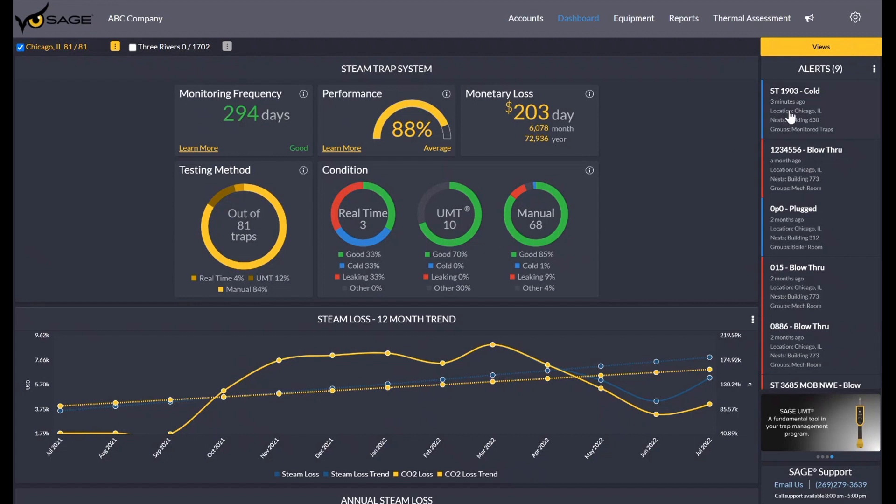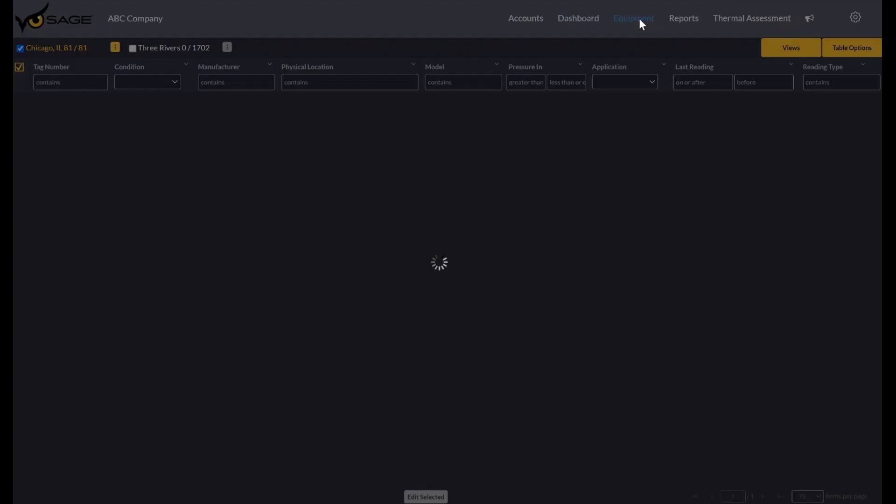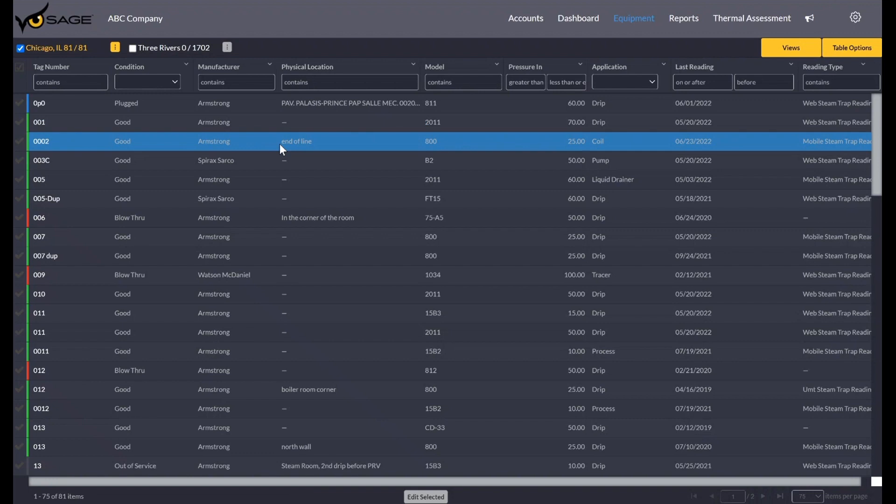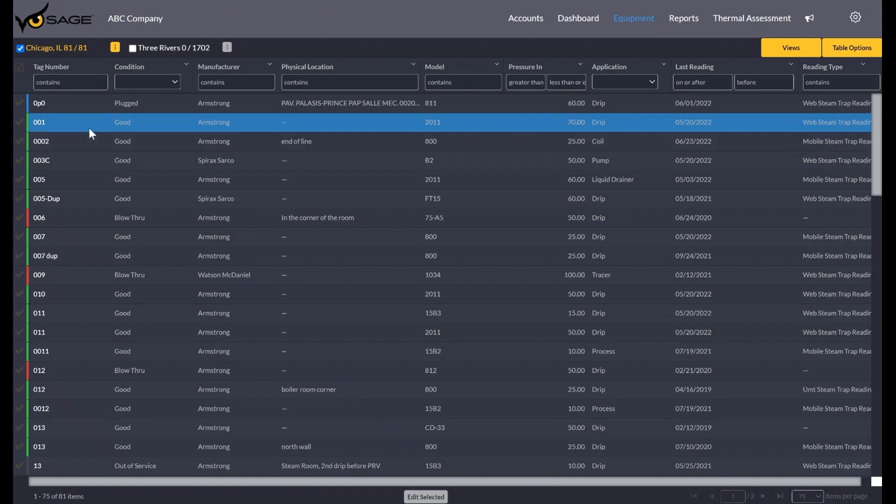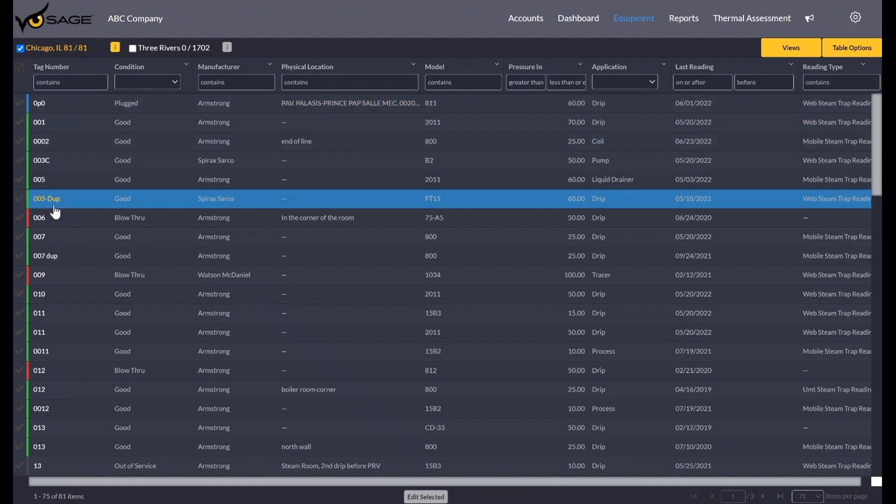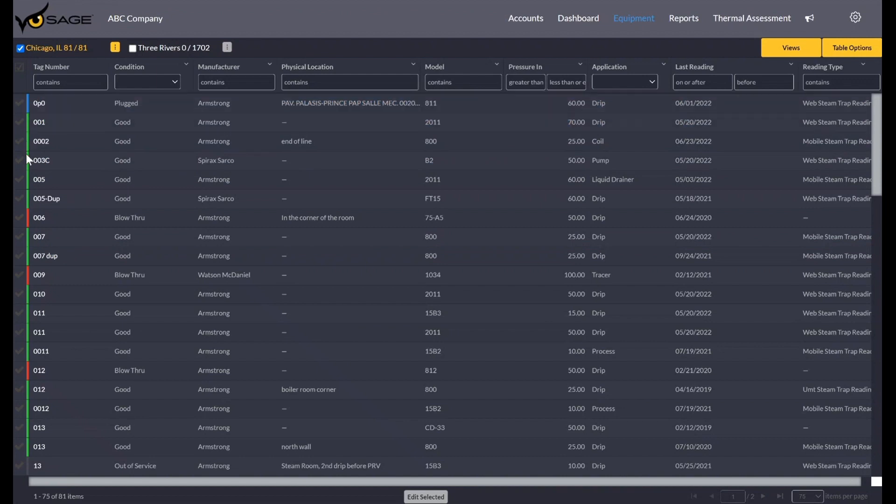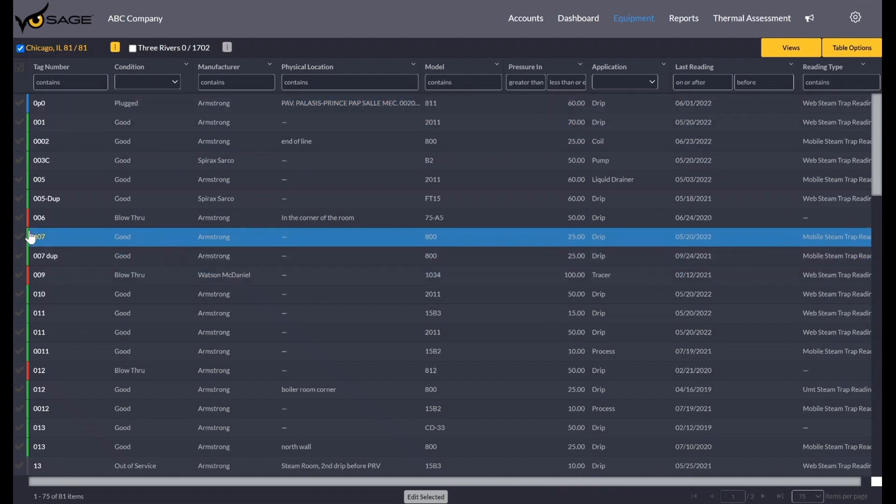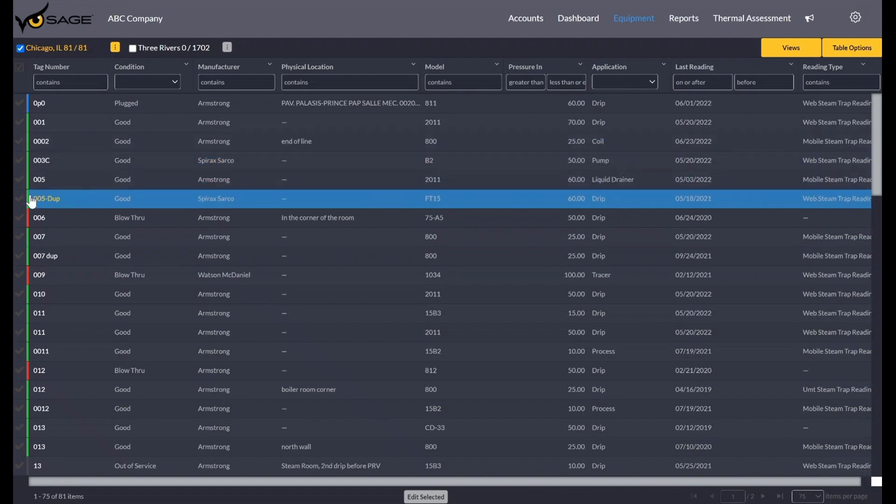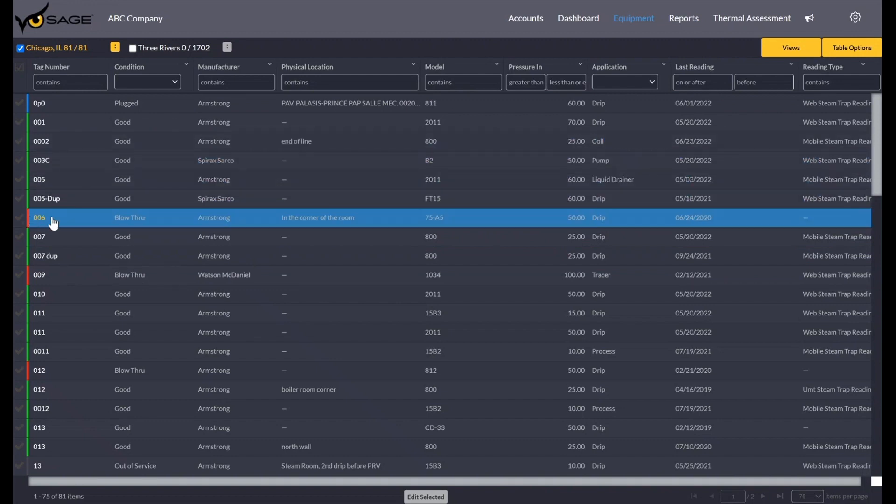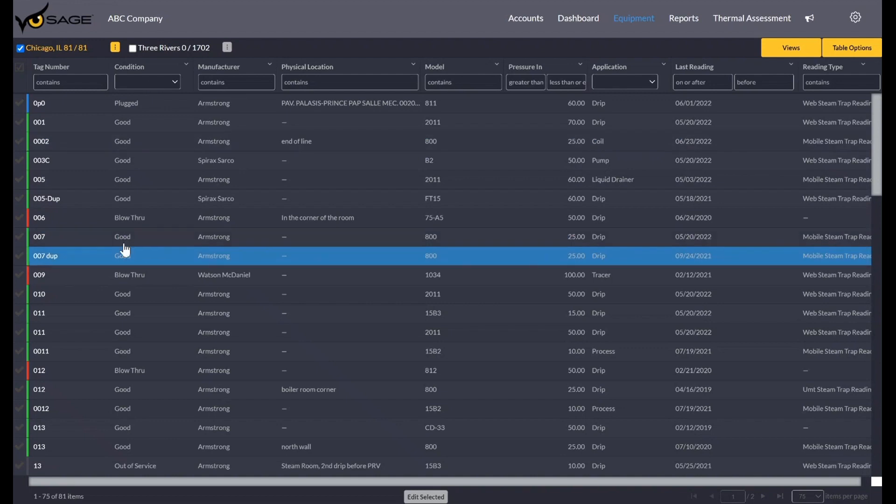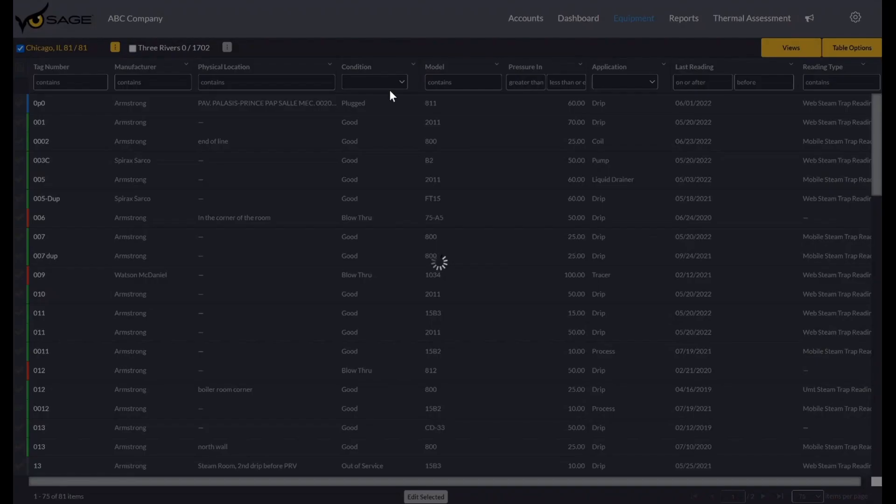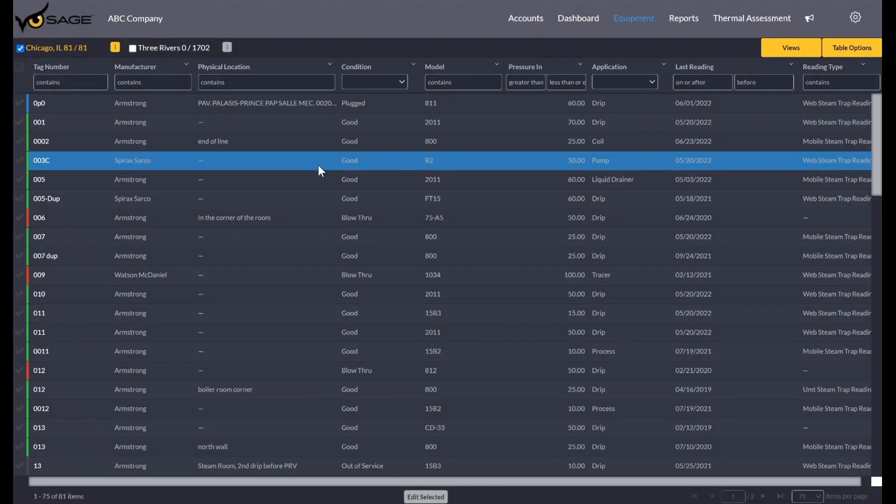You could click through to look at one of these tag numbers if you wanted to from the alert screen, or you could navigate to the equipment screen by clicking here. And here you'll see it's just a list of your population. The default sort is by tag number. You have the condition colors that you kind of saw on our dashboard there. You can see it's kind of glanceable. The green means all these traps are good. Red indicates a blow through. I have my condition column set as my second column but someone could move it along.